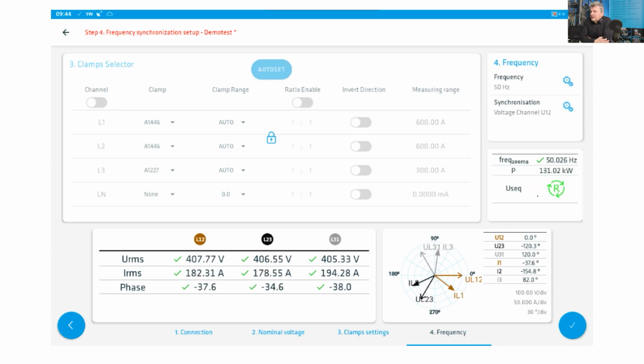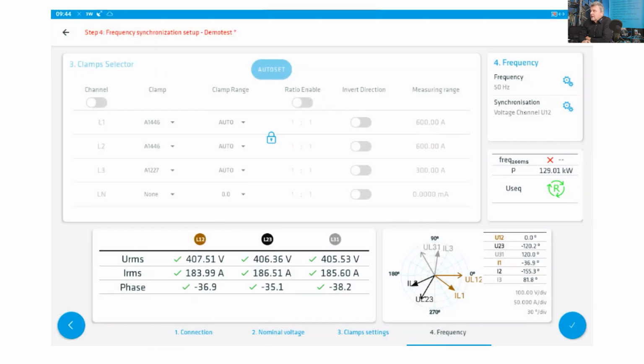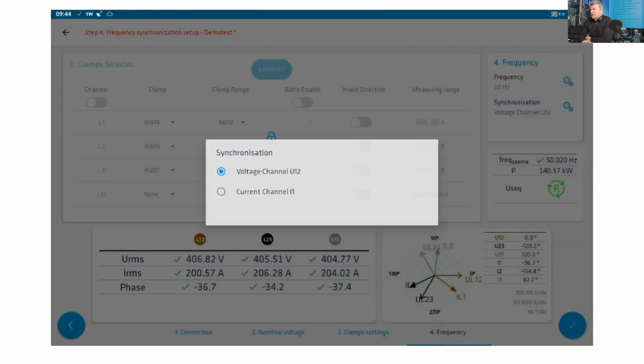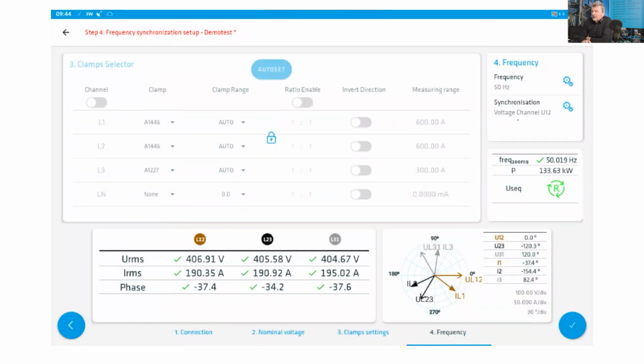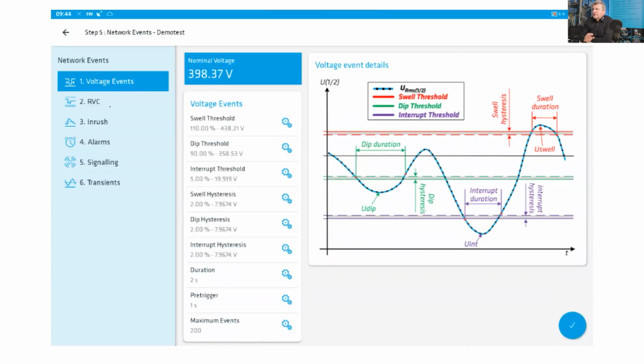The last setup is related to the frequency selection. You can use 50, 60, VFD or 400 Hertz, and also a synchronization channel, which you can select between voltage and current. Since the voltage is much more stable than the current, we suggest using the voltage channel. If you are satisfied with the connection and the online connection check, and we have yellow or green arrows, we can go further, which takes us to the setup of the network events.